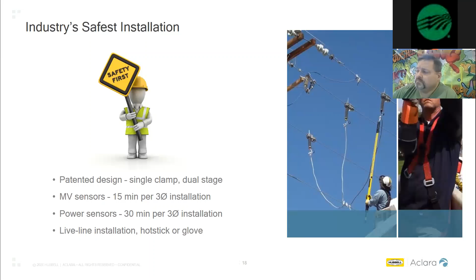The same thing happens exactly with the power sensor. The same style two-stage clamp will connect onto the conductor and secure it from sliding from end to end. Also, the important thing to know is that if you have any instances where you have a Hendrix type cable or an insulated cable in the field, the MV sensor will still operate on a coated cable. There's no need to remove that and have a bare metallic connection. We'll still be able to power the CT and generate power from that to operate the sensor. On the power sensor, in that case, you would be required to scrape that insulator back to make a metallic bare connection. So the clamp has a physical connection to the metallic conductor, and therefore gives us that path to the neutral or to ground from the bottom of the resistor.